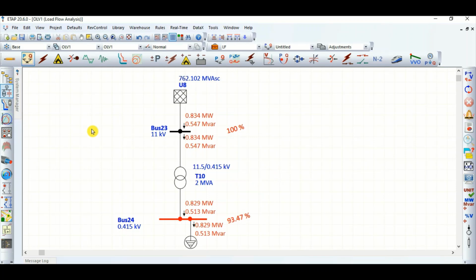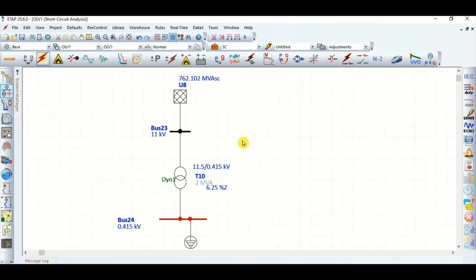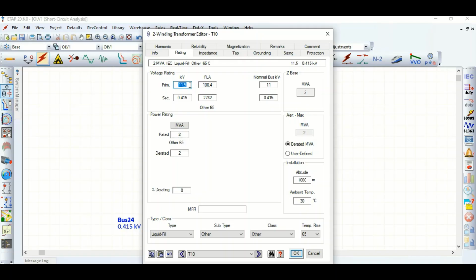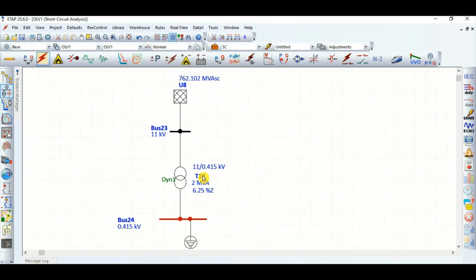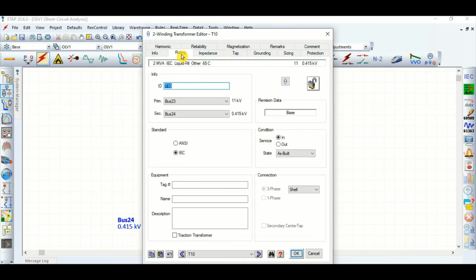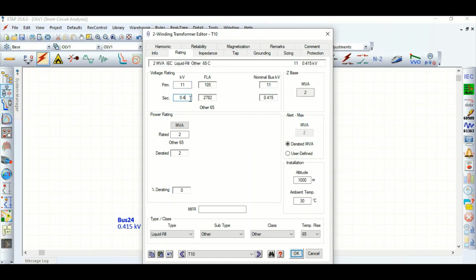Now we will check from the short circuit perspective what the impact may be. Let's take the normal value, 11 by 0.415 kV, without changing any other parameters. I'll simply run the short circuit. This is the fault level at 415 volt. The bus fault level is 53.219 kiloampere. Now let's change this to 433 volt.